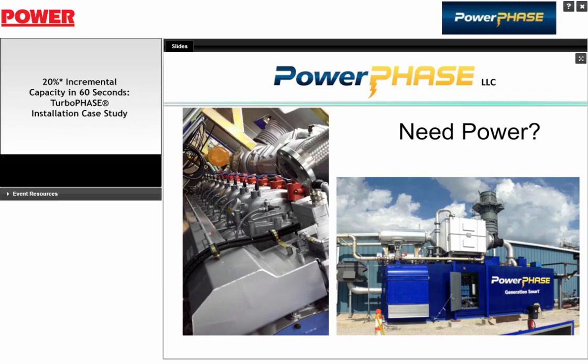All right. What about the question, why not use electric drives? It's pretty simple. If we had an electric motor in our system generating 3 to 3.5 megawatts out of the 6B, we'd only be netting out 1.5 to the grid. And when you do the dollars per kW, it looks really, really bad. It's doubling the installed dollars per kilowatt cost.